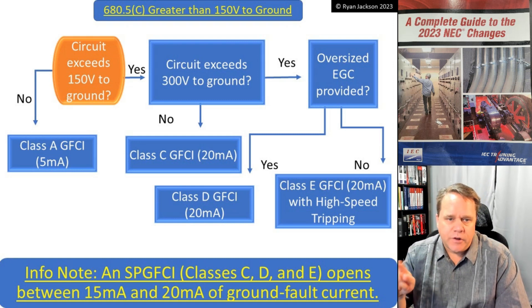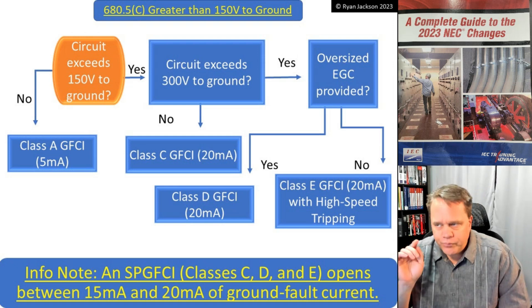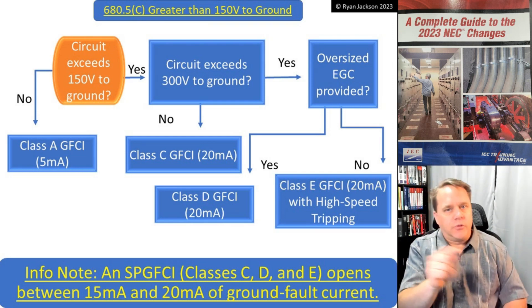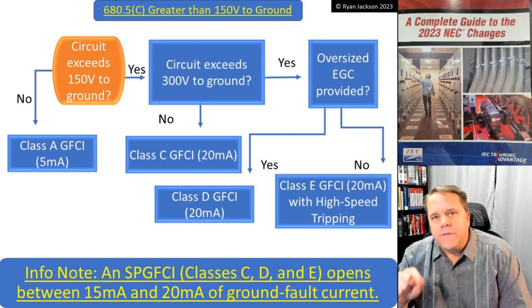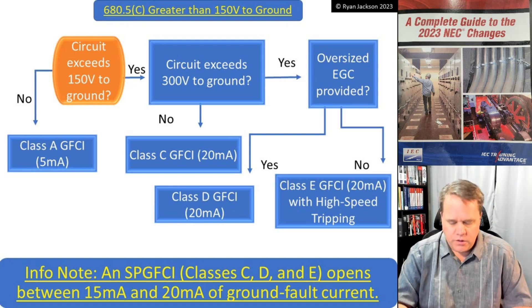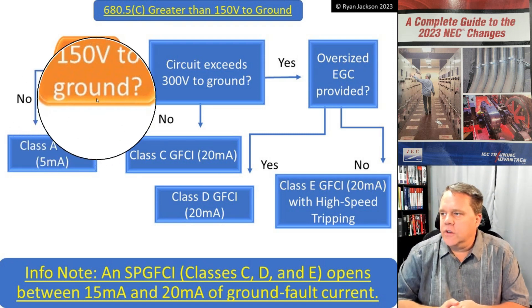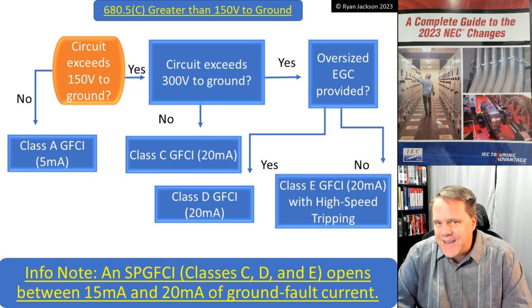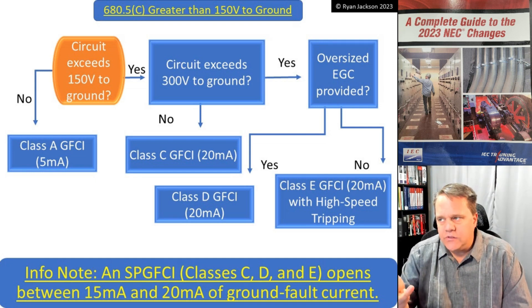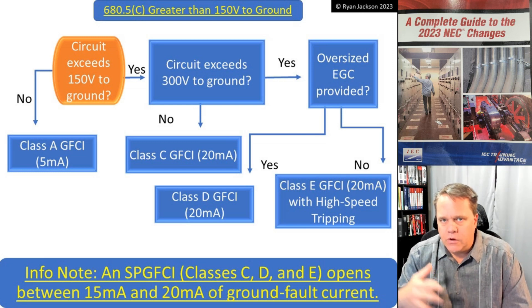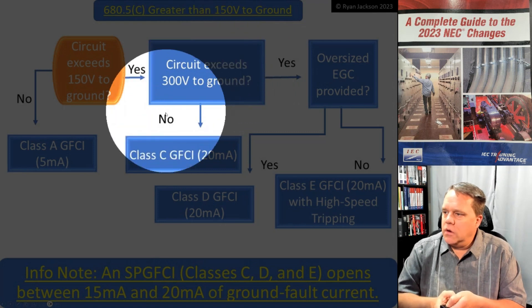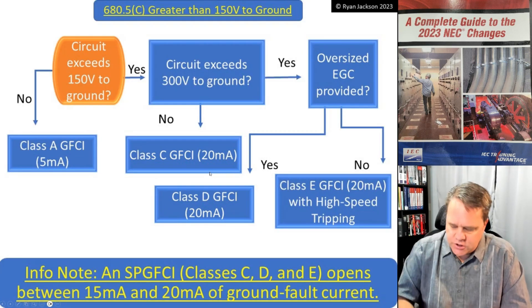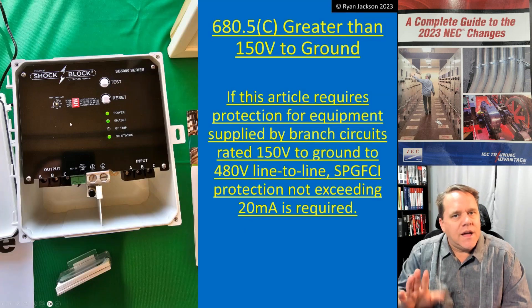Looking at the flow chart: starting at the orange one — if the circuit does not exceed 150 volts to ground, then we use Class A GFCI protection, which opens between four and six milliamps. What if the circuit does exceed 150 volts to ground? Then we keep reading and ask: does the circuit exceed 300 volts to ground? A 277/480-volt Y-connected system does not exceed 300 volts to ground. So if it's 277/480, the answer is no — I'm going to install a Class C GFCI, which operates at 20 milliamps. I would dial in the setting to 20 milliamps on that protection device.